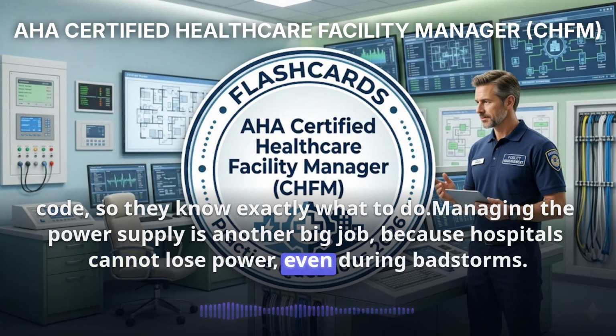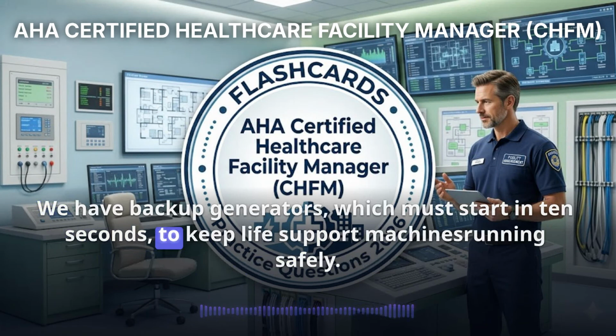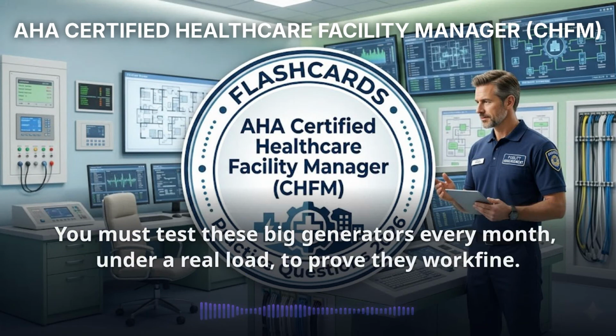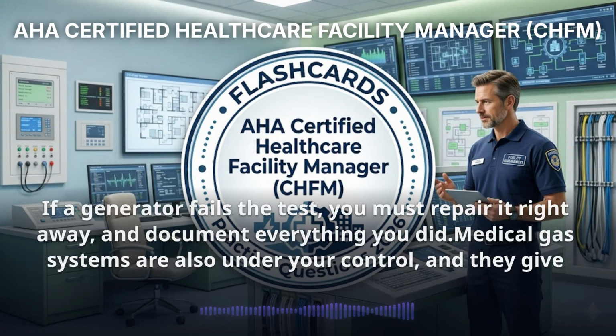We have backup generators, which must start in 10 seconds, to keep life support machinery running safely. You must test these big generators every month, under a real load, to prove they work fine. If a generator fails the test, you must repair it right away, and document everything you did.